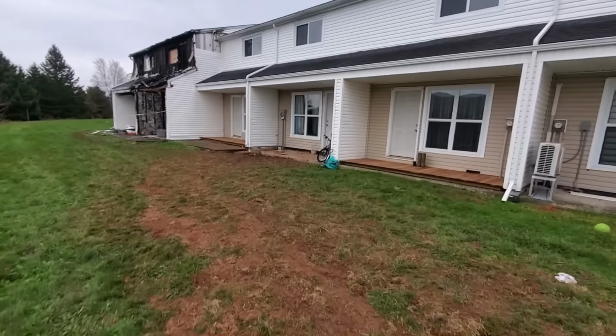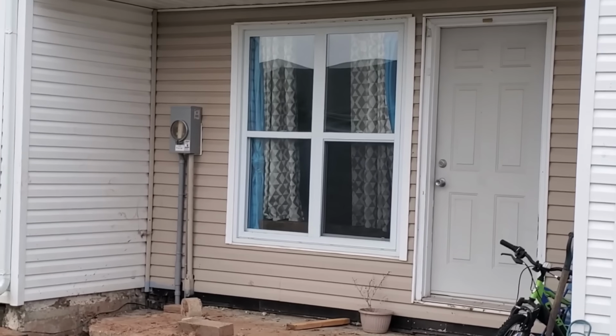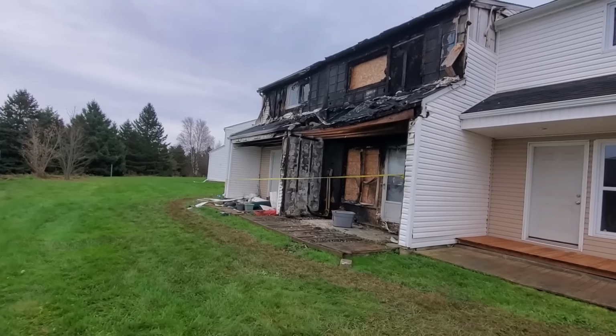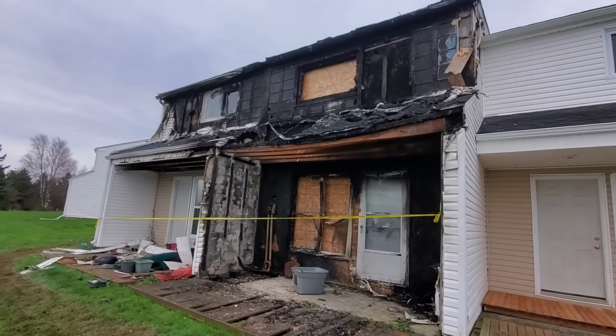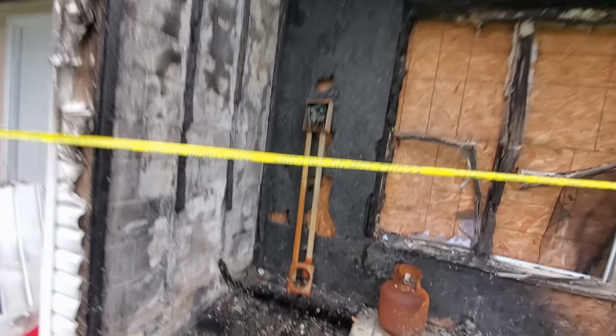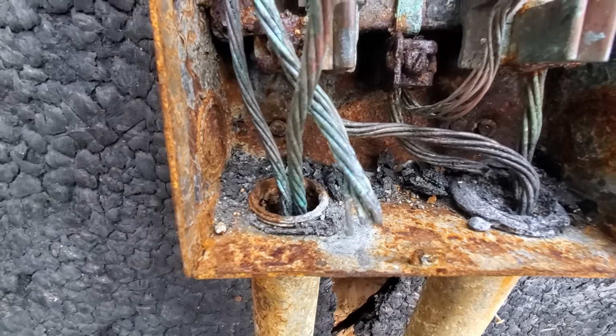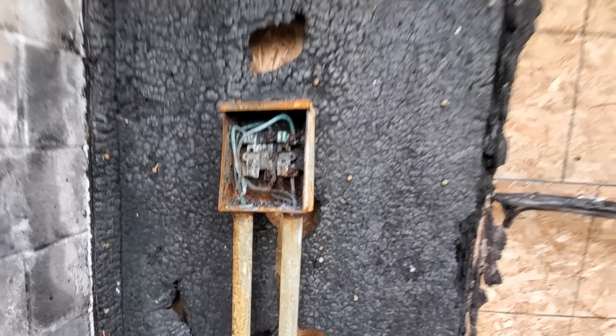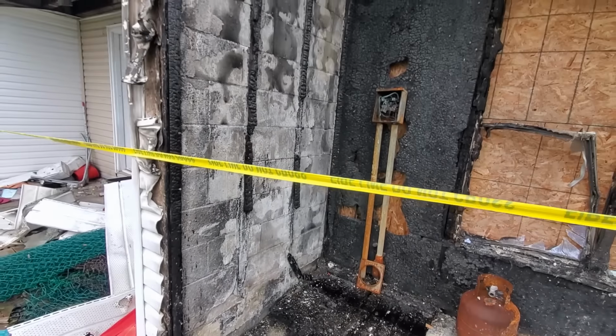But in order to run that wire over into our box and make the final connection, the pipe's not yet connected into our pad mount for the main cable to the box. In order to dig near that, we have to have those cables de-energized. So while the electrician is going to be digging in our work area near the high voltage cables, we're going to be replacing that pad mount with a brand new one, and also sorting out all those secondary runs, kind of taping them together so that we know which two hots go to which house.